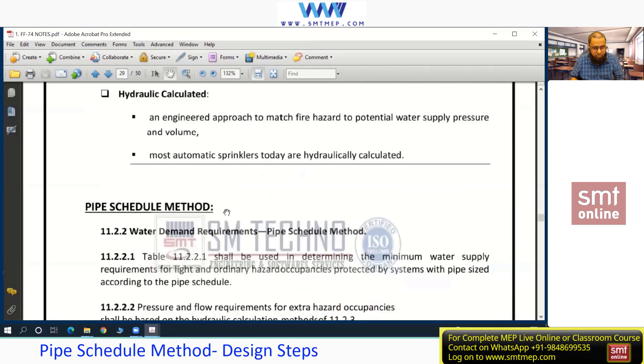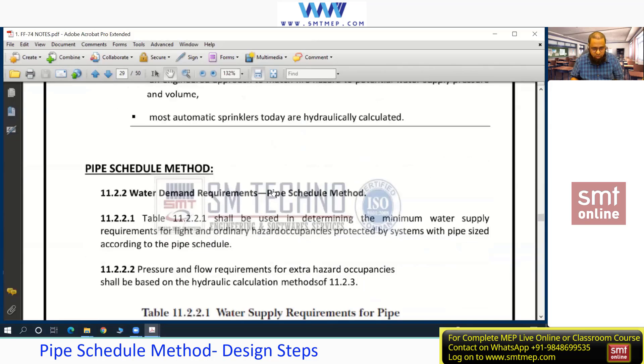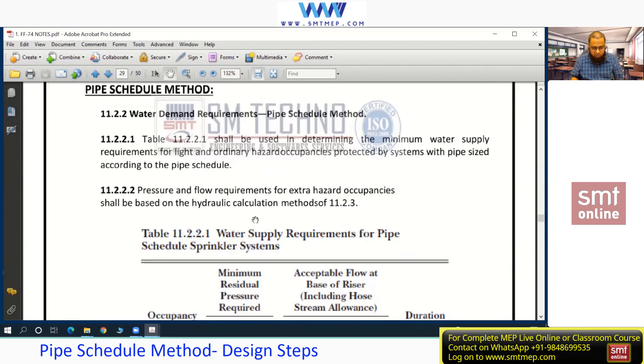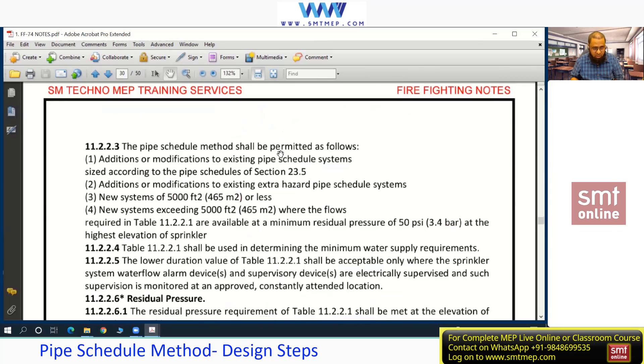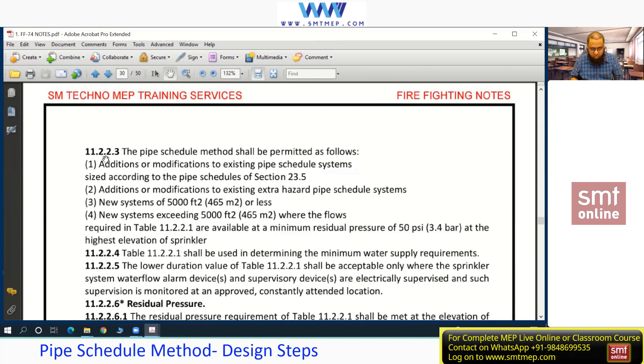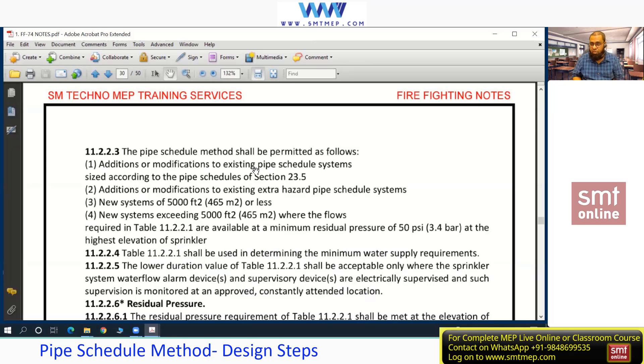On screen you can see the pipe schedule method. The important points are in the notes. Directly, condition 11.2.2.3 states: the pipe schedule method shall be permitted for additions or modifications to an existing pipe schedule system — meaning if a project was already done with the pipe schedule method, any addition or modification can follow the same method. For a new system, it is allowed up to 5,000 square feet or less.